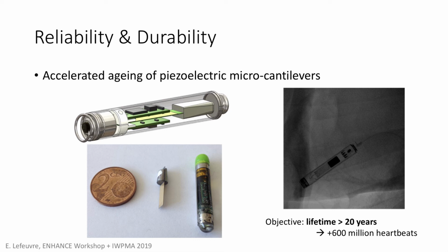So the cantilever itself was presented, but I show it again. It's here. It's composed of a very thin piezoelectric beam. It's a PZT bimorph made of bulk material thinned by mechanical etching, mechanical grinding. And this is the tip mass, and this side is bonded on the capsule. So it oscillates. So you have here an artist view of the cantilever beam, the proof mass, and the capsule all around with the electronics and the screw to attach the pacemaker to the heart.